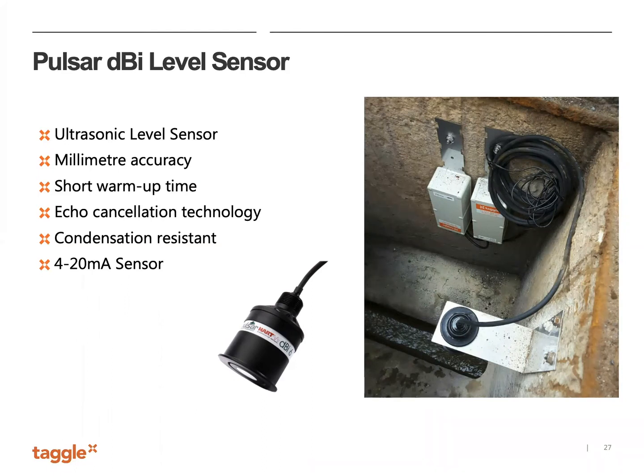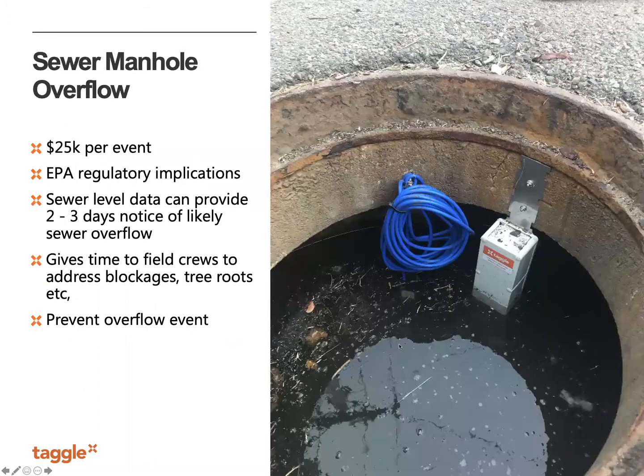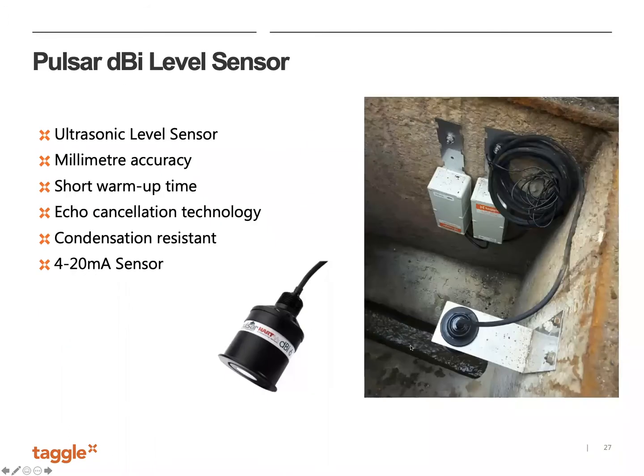This sensor is quite clever in that it has echo cancellation built into it, so it knows what it should be listening to and what it shouldn't. For example, the echo off the concrete apron around the pipe doesn't mean anything, so it will ignore that reflection and concentrate on the sewer wastewater level, which is the water you can see in the pipe down there. That'll provide millimeter level accuracy.